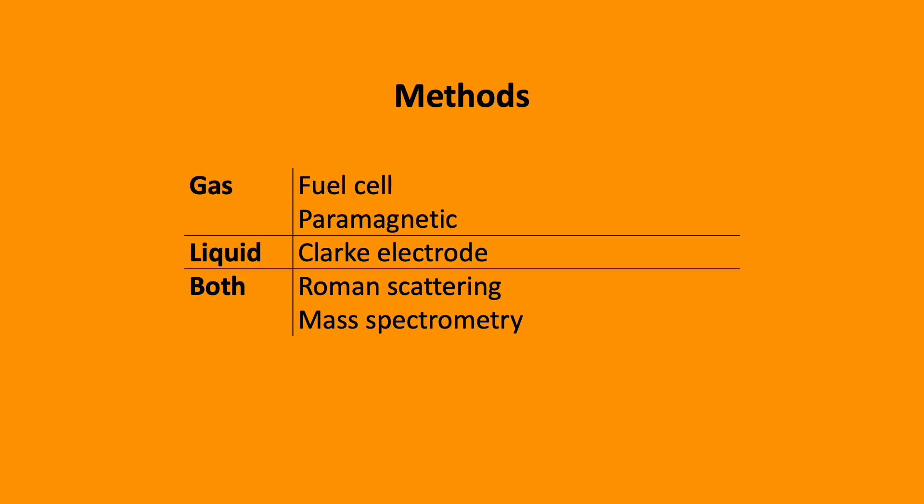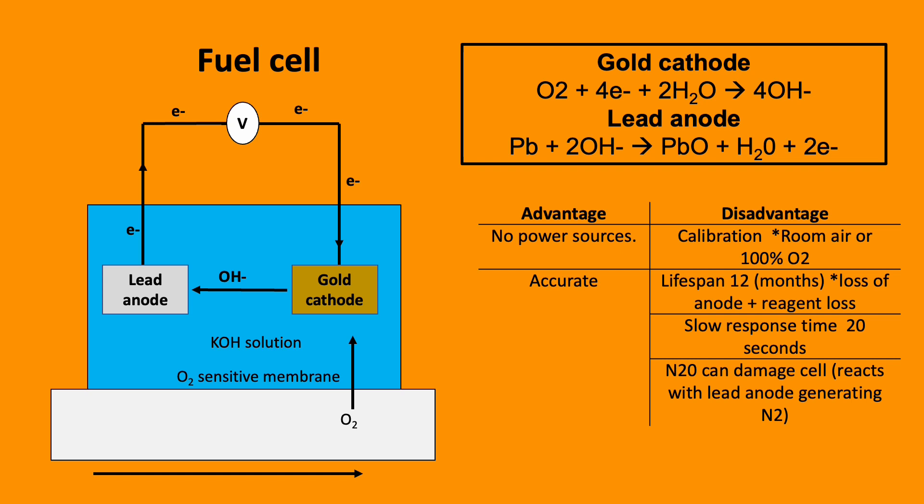Other methods include Raman scattering and mass spectrometry. The fuel cell is a device composed of a lead anode, gold cathode, potassium hydroxide solution, and O2-sensitive membrane. It's located in the inspiratory limb of the breathing system.